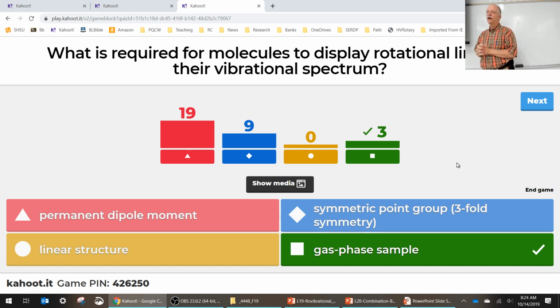But FTIR is everywhere. And so you won't see rotational lines in your FTIR spectrum unless you have a gas phase sample. And you do see them in almost every FTIR because you have water and CO2 in the atmosphere. So even though you're taking a liquid or solid sample, if you see some rotational lines, that's probably not your liquid or solid sample. It's something in the air around your sample, either in the spectrometer or in the little sample chamber. Most of the time it's water and CO2. But one time I told you I sprayed methanol in there and I got nice rotational spectrum.